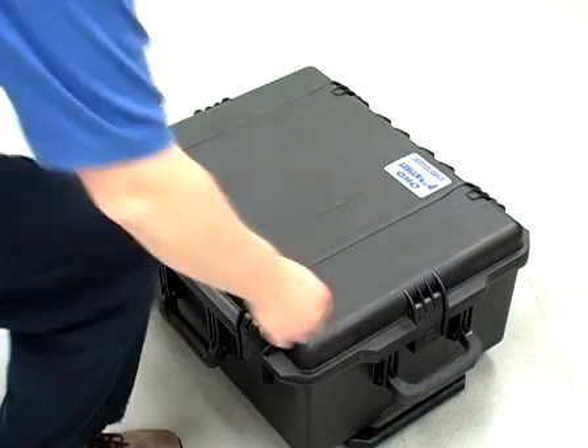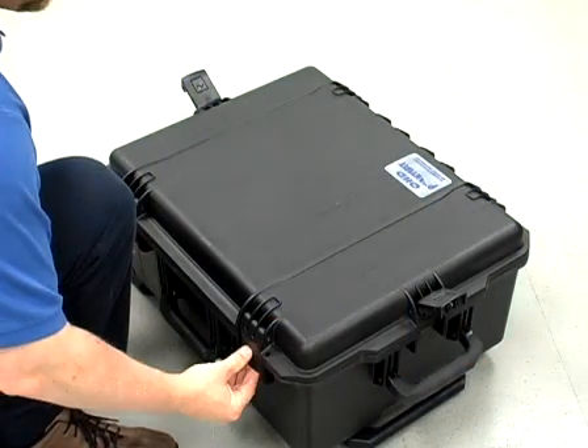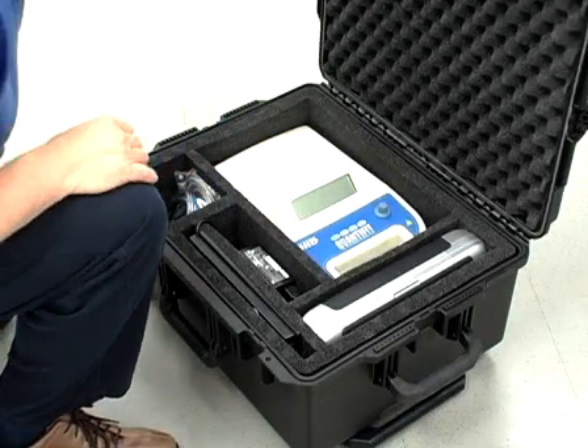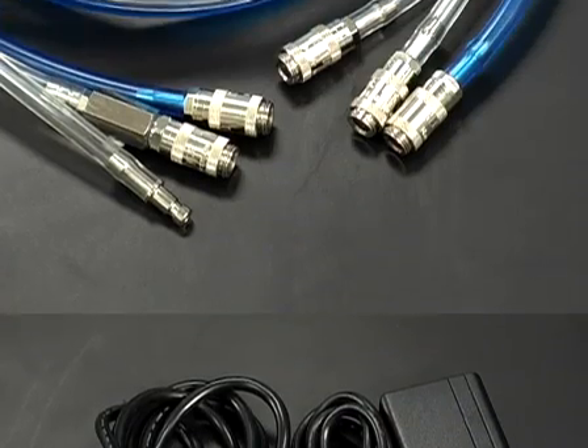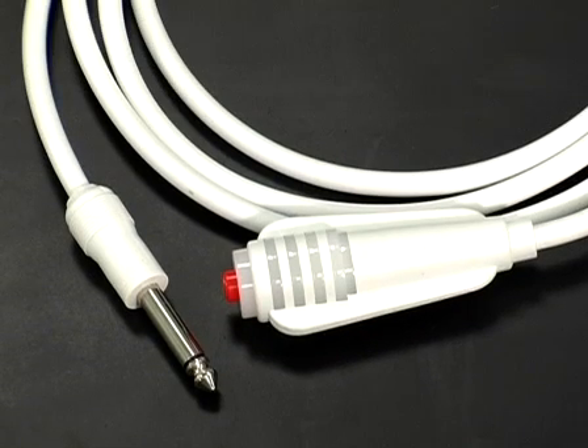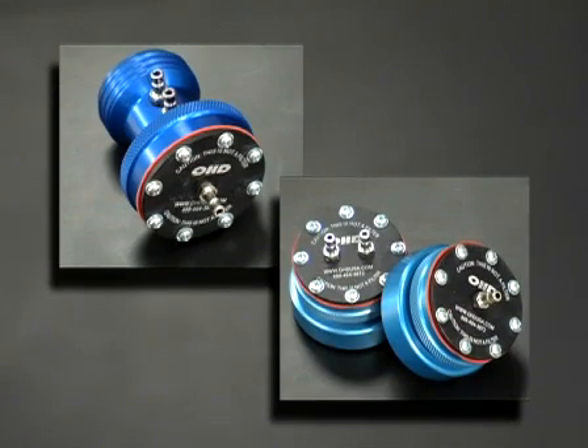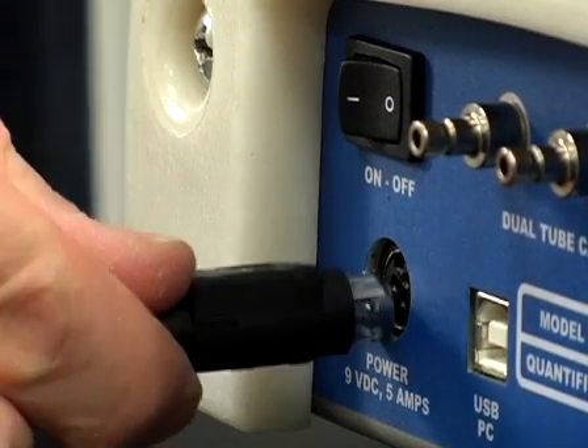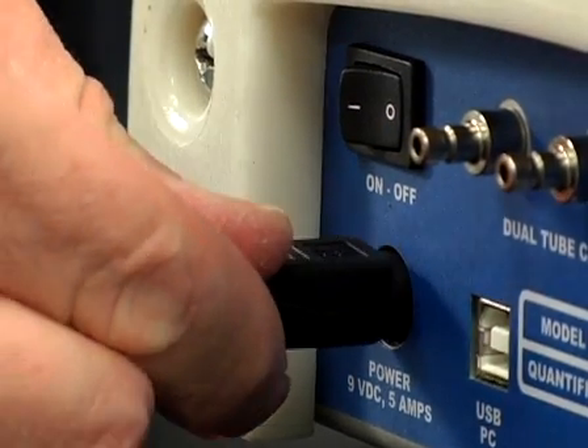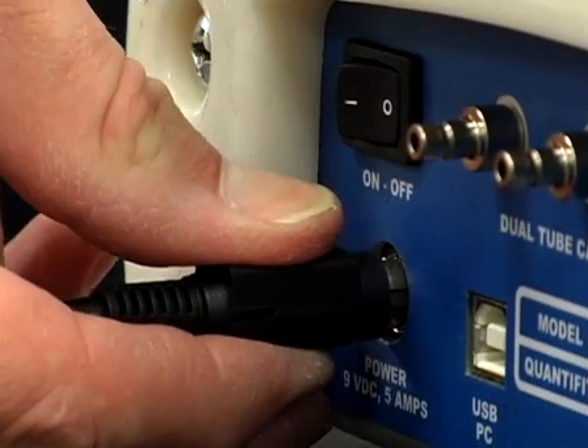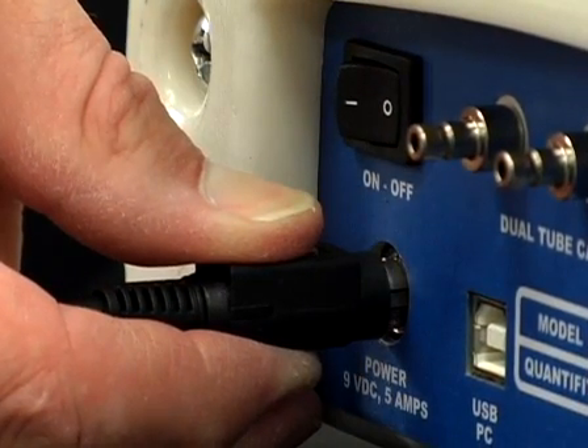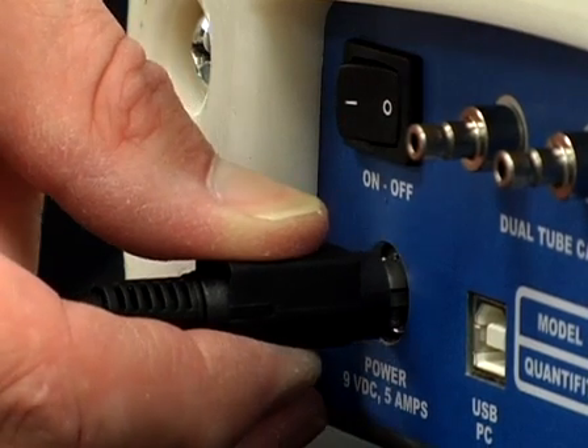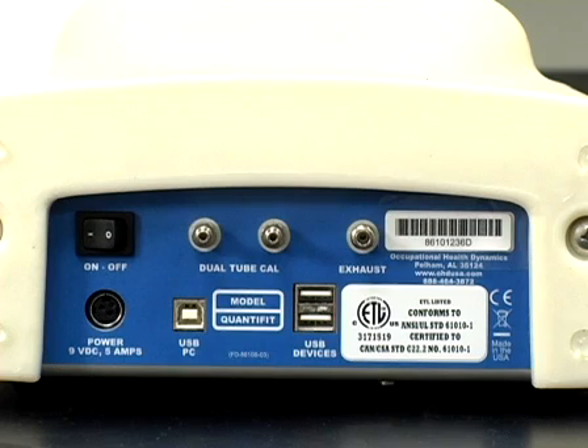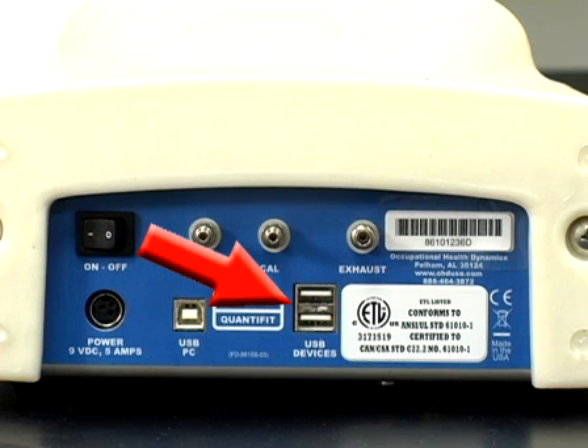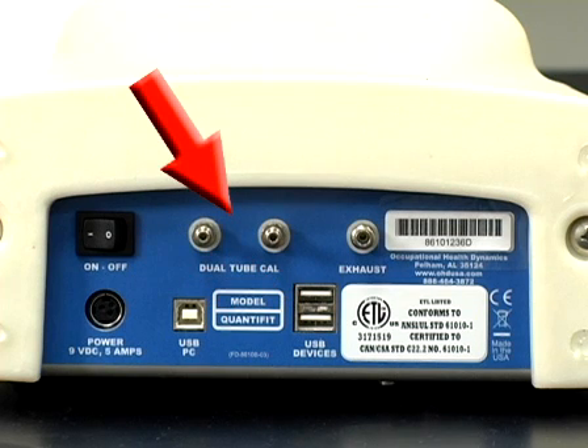Your case contains all the cables and attachments needed to do a proper fit test. You'll need the power cable, the triple hose assembly, the white trigger button, and the fit test adapter. When inserting the power supply, the flat side should face up. When removing the power cord, you must pull on the portion with the flat top in order to release the cord lock. On the back of the instrument, you will also find connections for PC interface, USB ports for keyboard, printer, and memory stick, and calibration ports.